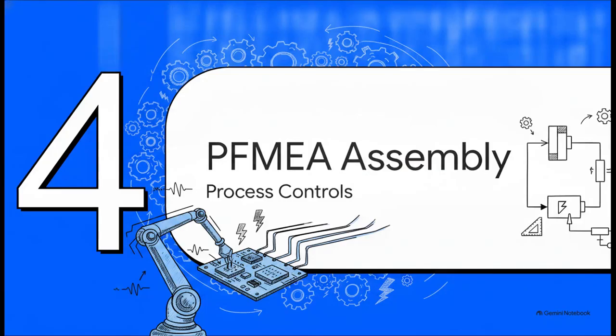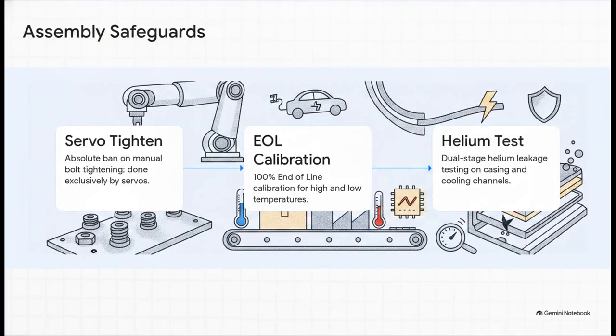Section 4, the assembly, focusing on PFMEA process controls. Because a brilliant design means absolutely nothing if you can't assemble it perfectly, right? Out on the factory floor, there are three primary manufacturing safeguards. First, an absolute ban on manual bolt tightening. It is exclusively done by precision servos. Second, 100% end-of-line calibration for high and low temperatures. This permanently writes voltage sampling corrections directly into the controller's memory for every single unit. And third, extreme dual-stage helium leakage testing to block moisture intrusion down to 10 to the negative fifth millibar.